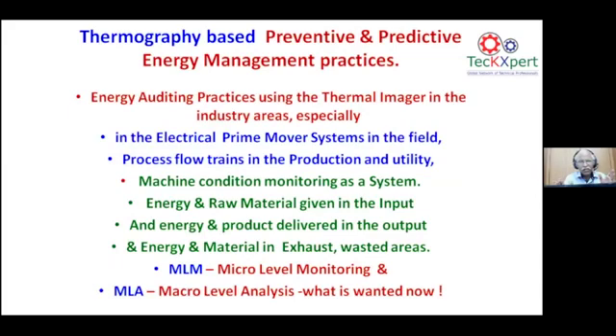Everywhere on the electrical side the thermal imager is used, but let us try to use the thermal imager on the process side. You can see the temperature gradient of the process. You can see the process flow trains in the production as well as in the utility. Thermal imager is an excellent, affordable and non-invasive tool to be used in each and every industry. Each and every industry should mandatorily have this thermal imager to see all the energy flows on the production and the utility side. And micro level monitoring is done by the low level people, and macro level analysis, MLM and MLA, both are wanted in the industry.